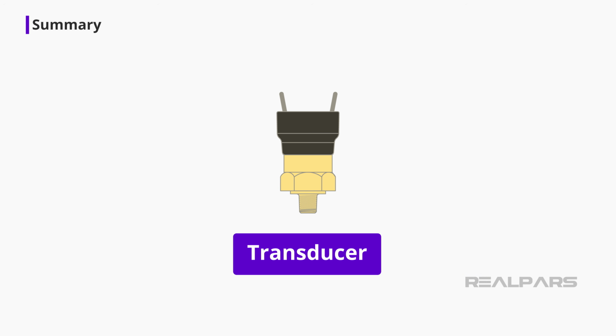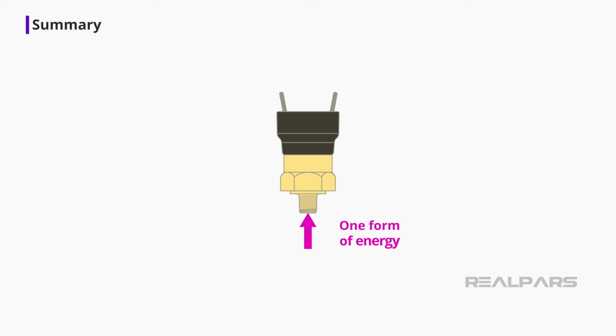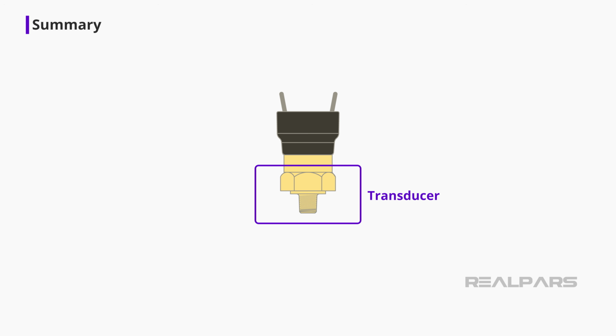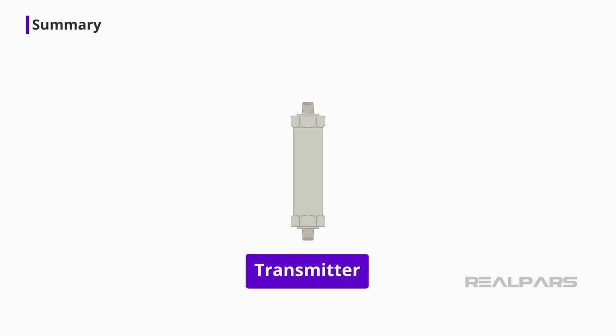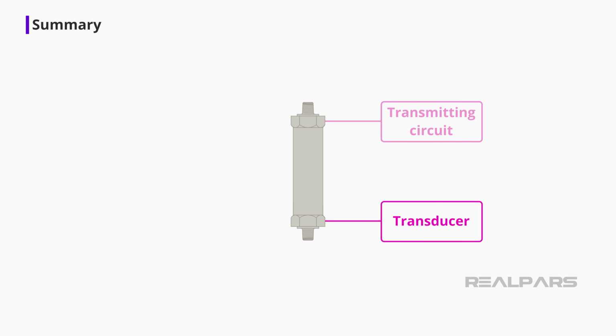Let's review. In process control and instrumentation, the terms transmitter and transducer are often used interchangeably. A transducer is a device that converts one form of energy to an electrical or electronic signal. A pressure switch is a two-part device consisting of a sensing transducer and an electrical switch. A pressure transmitter is a two-part device consisting of a sensing transducer and a circuit that transmits a standard instrumentation signal, which in most applications is 4 to 20 milliamps.